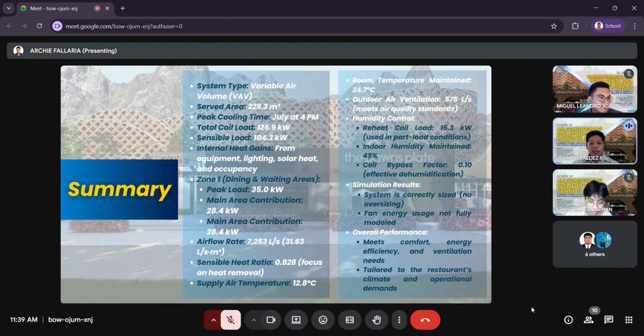Supply air is cooled to 12.8 degrees Celsius to maintain a room temperature of 24.7 degrees Celsius, with outdoor air ventilation at 575 liters per second, meeting indoor air quality standards. A reheat coil load of 15.3 kilowatts supports humidity control during part load conditions. The system efficiently dehumidifies with a coil bypass factor of 0.10, maintaining indoor humidity at 45%. Simulation confirms the system is correctly sized without unnecessary oversizing. Though fan energy usage was not fully modeled and may require further analysis, overall the design meets comfort, energy, and ventilation needs for the restaurant's specific climate and usage.